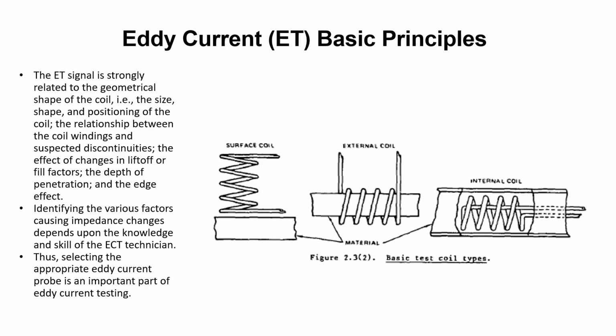The eddy current testing signal is strongly related to the geometrical shape of the coil, i.e. the size, shape, and positioning of the coil. The relationship between the coil winding and the suspected discontinuities, the effect of change in lift-off or fill factors, the depth of penetration, and the edge effect. Identifying the various factors causing impedance changes depends on the knowledge and skill of the eddy current testing technician. Thus, selecting the appropriate eddy current testing probe is an important part of eddy current testing.